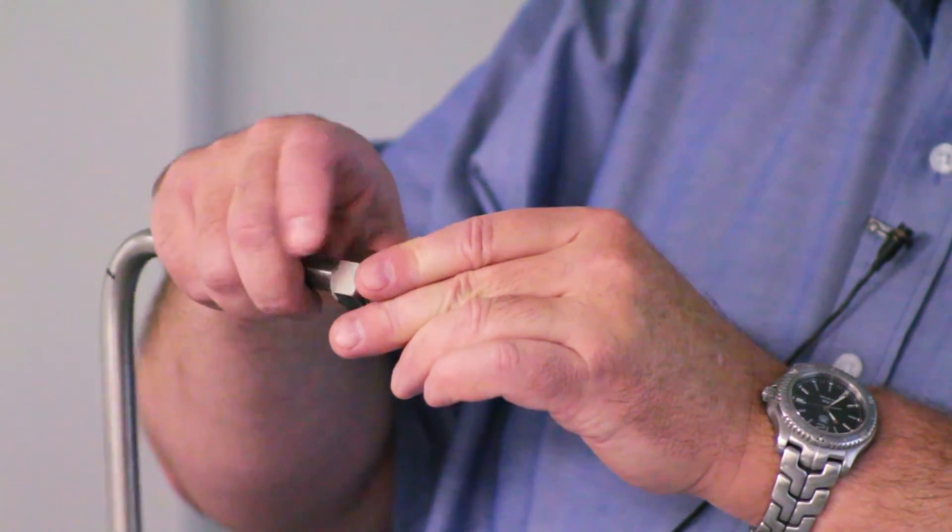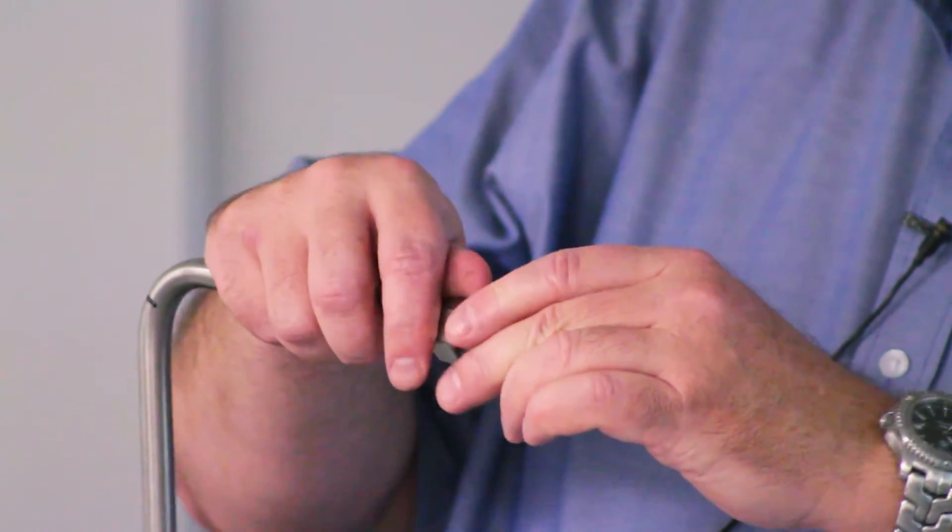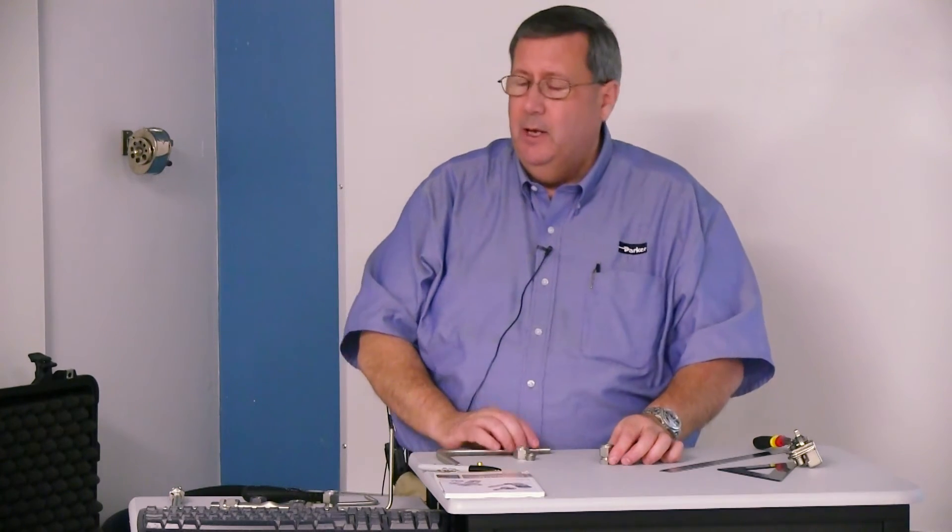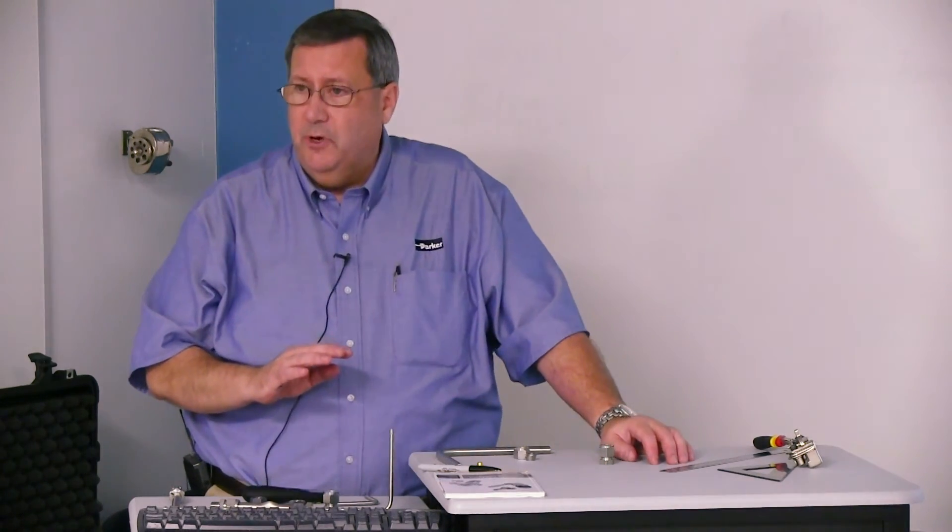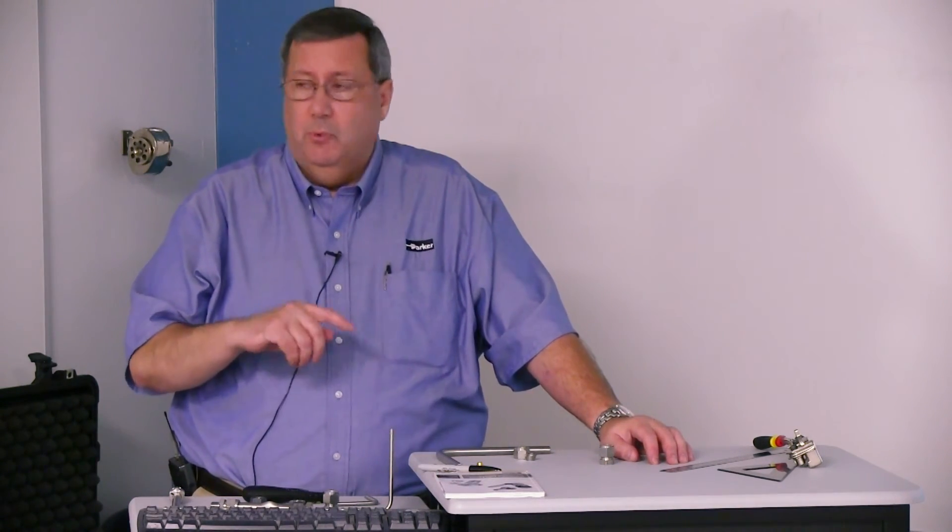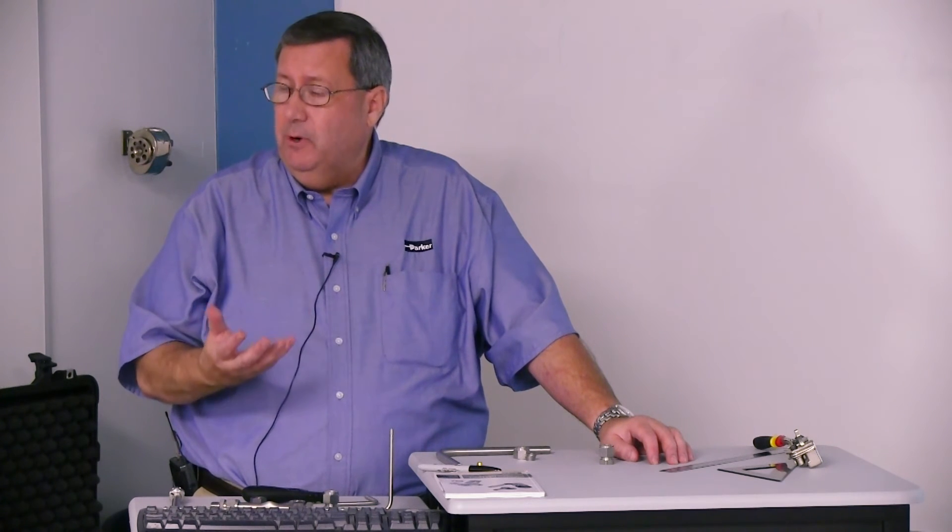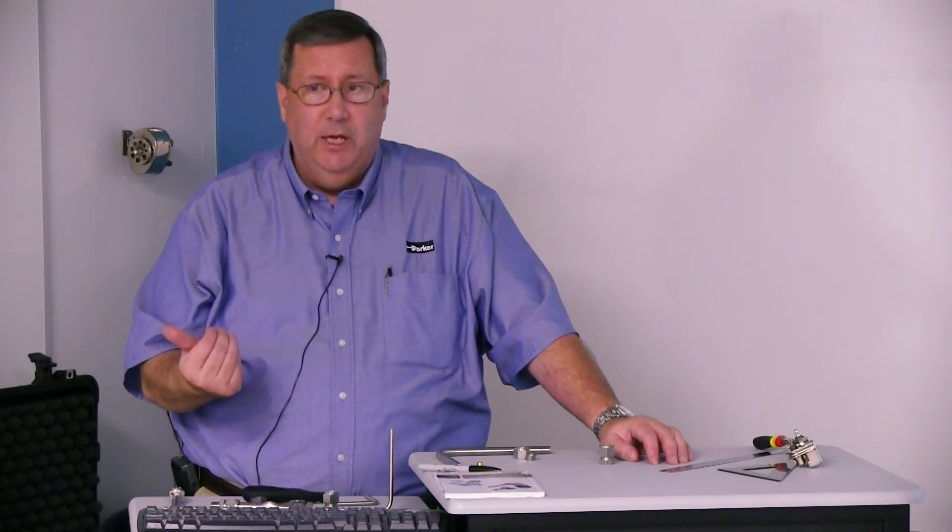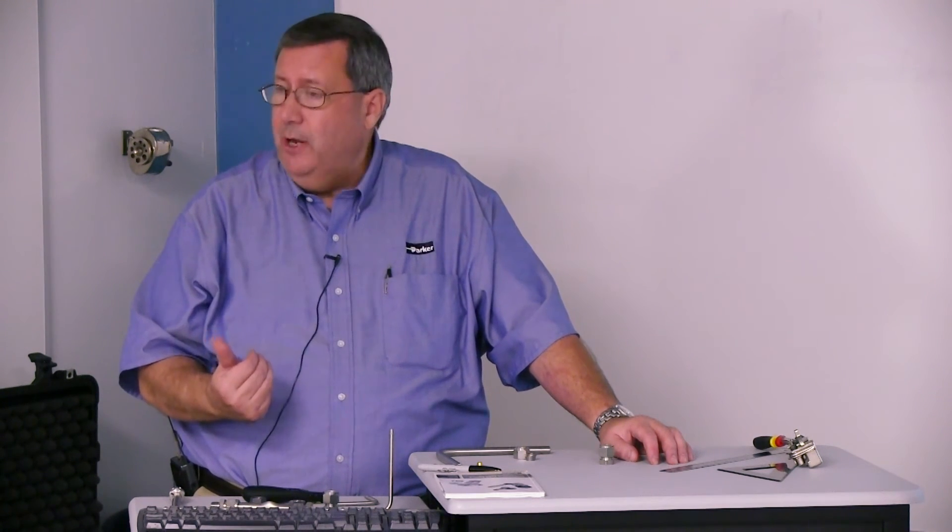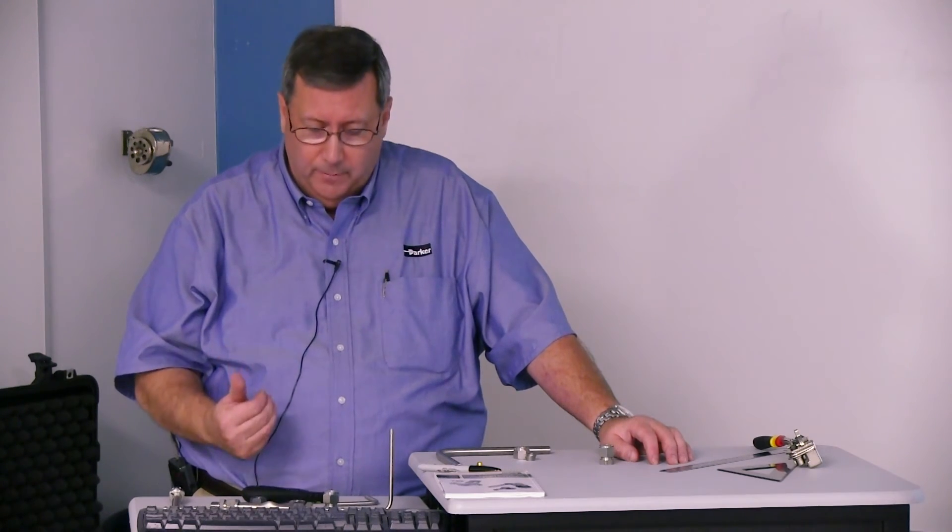Then you know the ferrule is in the right orientation. The most common mistakes with a two-ferrule system are putting the rear ferrule in backwards or leaving the rear ferrule out. In both cases, you're going to have leakage, and if you go to high pressure, you're going to have a blowout. That's very important to learn.